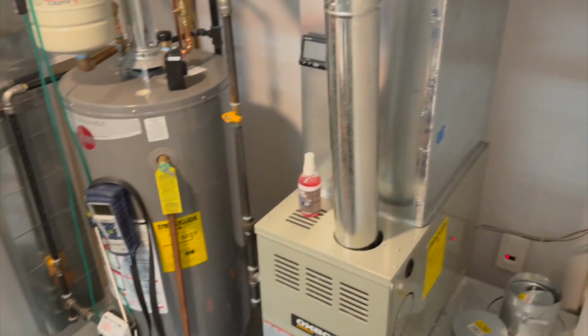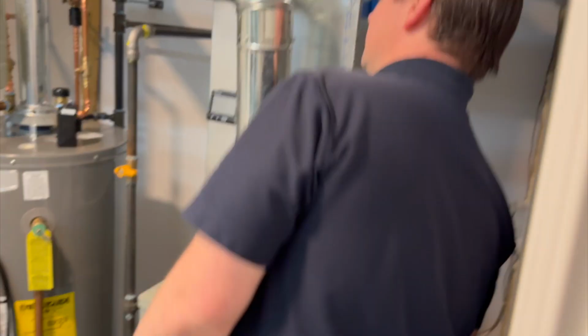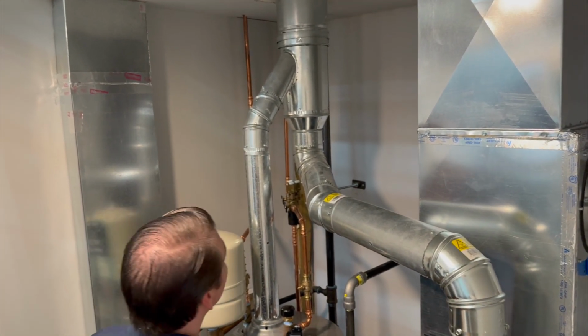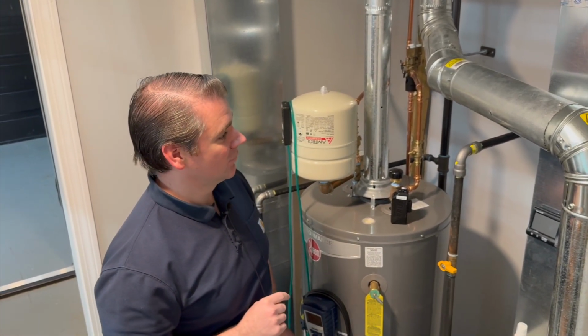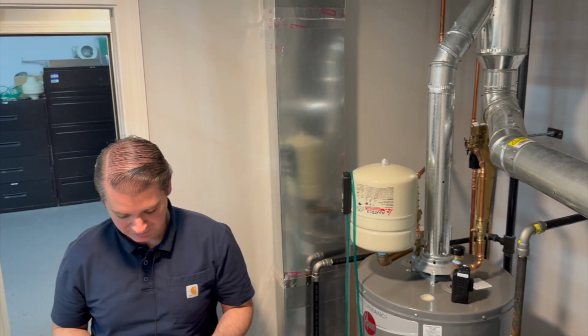Identify and describe 2 acceptable methods for temporarily disabling mechanical equipment. We've got our service switch right behind the corner, or we can turn off the breaker at the electrical panel. Do a visual inspection of the flue system for the combustion appliance and identify and discuss concerns or problems. If no deficiencies, discuss one common concern or problem. So let me examine our flue piping real quick. I don't see any signs of rust or corrosion. One of the common defects would be the flue pipe itself is back-pitched, so it's sloped downwards. We always want to maintain that minimum 1/4 inch rise per foot.